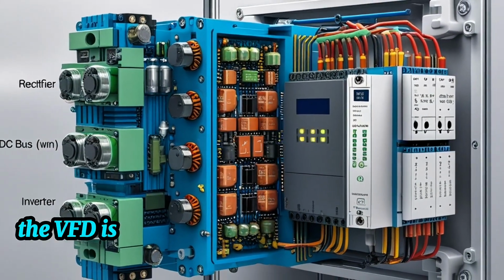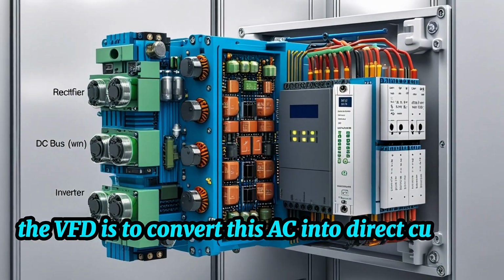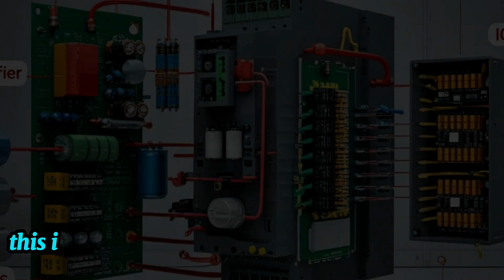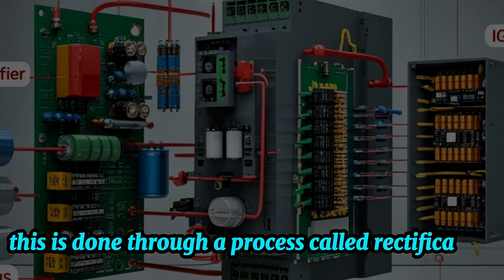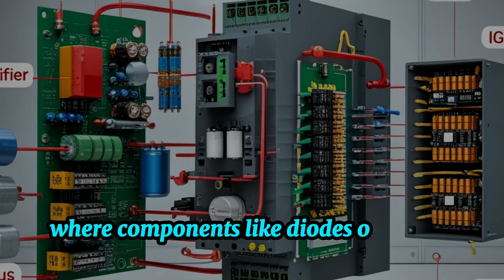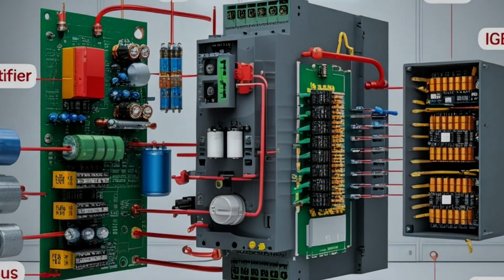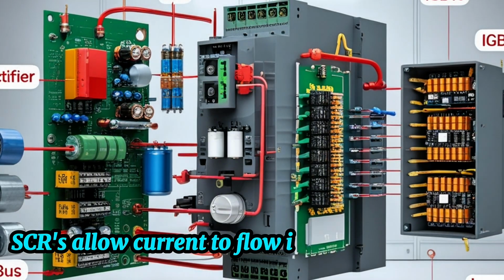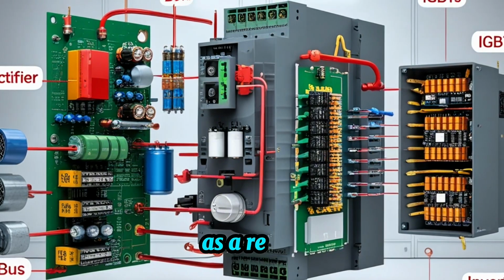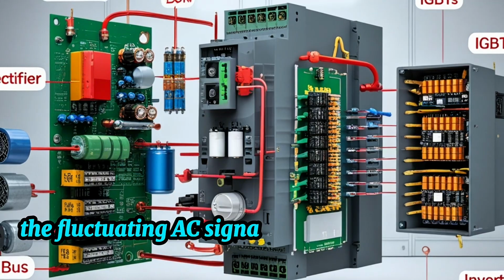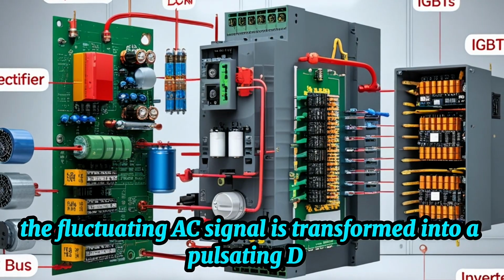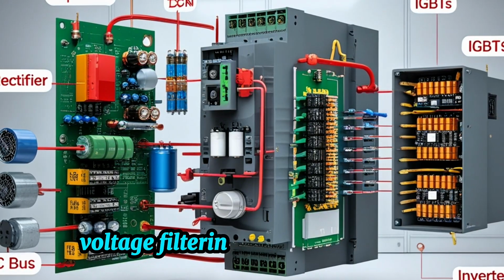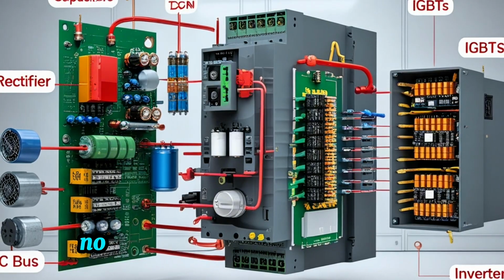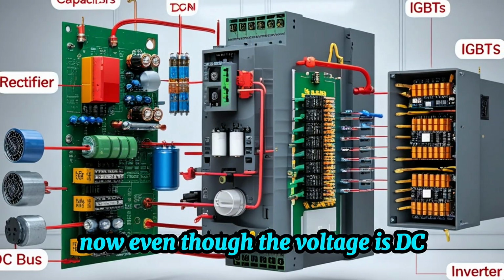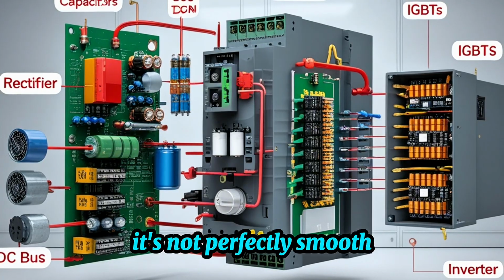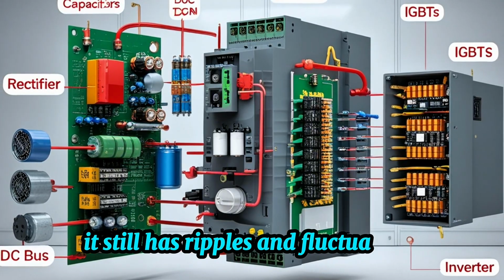The VFD is to convert this AC into direct current, DC. This is done through a process called rectification, where components like diodes or silicon-controlled rectifiers, SCRs, allow current to flow in only one direction. As a result, the fluctuating AC signal is transformed into a pulsating DC voltage. Filtering, smoothing the DC. Now, even though the voltage is DC, it's not perfectly smooth. It still has ripples and fluctuations.